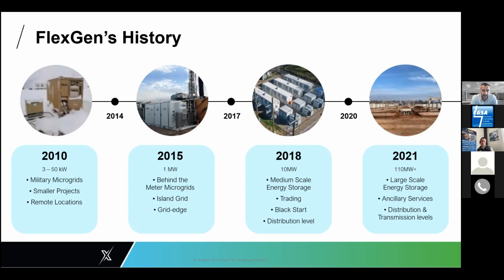I think to add a bit more about asset selection - there's great variability in the capabilities of different inverters or PCSs out there, those terms are kind of interchangeable. Ageto has a few projects operating where the backup battery system takes about 2 minutes to back up the site and boot up to black start it, whereas other inverters can go from 0 to full power in under 10 milliseconds, directly controlling the islanding contact or motorized circuit breaker. So in that case, the entire factory can be backed up seamlessly if there's a fault in the utility grid, and you don't have to have the big UPSs for continuity on site.